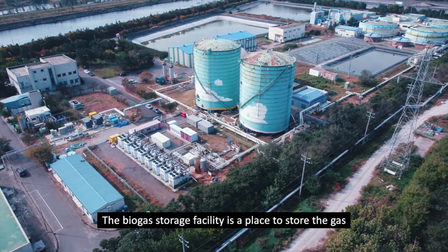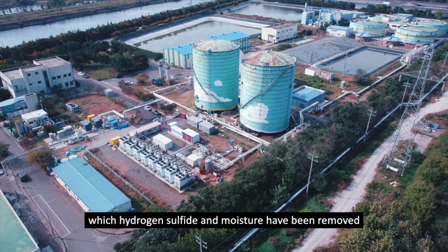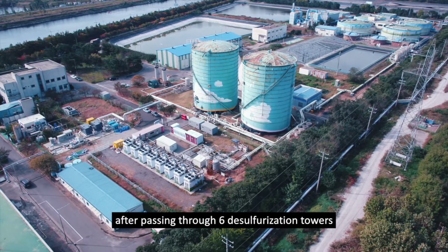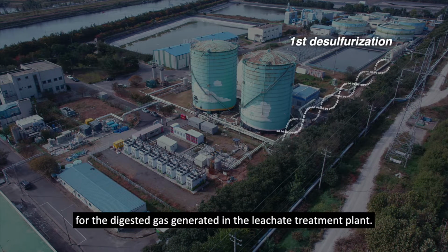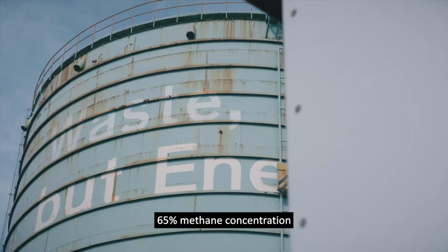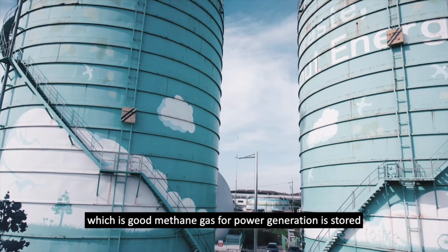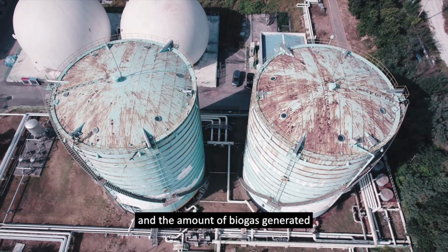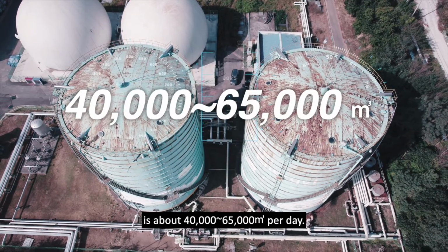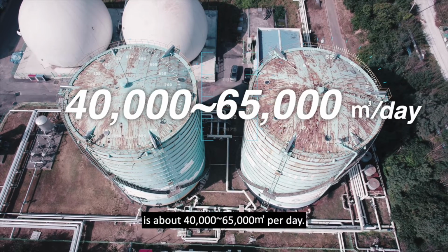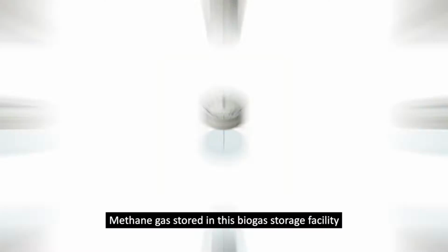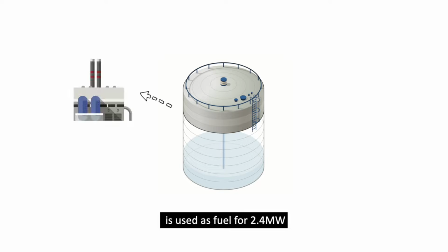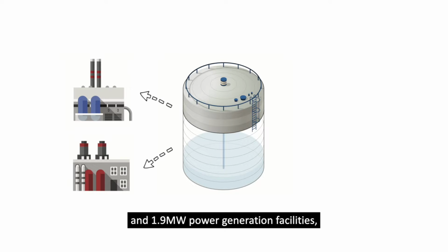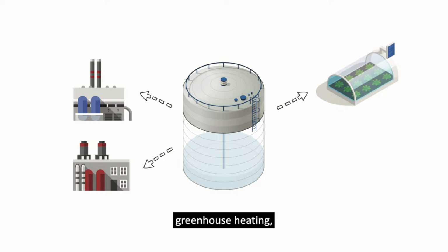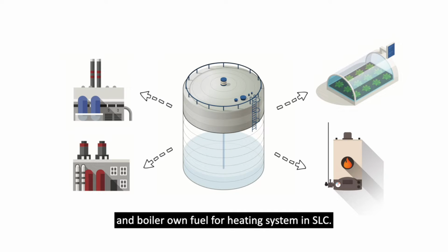The biogas storage facility is a place to store the gas from which hydrogen sulfide and moisture have been removed after passing through 6 desulfurization towers for the digested gas generated in the leachate treatment plant. A 65% methane concentration, which is good methane gas for power generation, is stored, and the amount of biogas generated is about 40,000 to 65,000 cubic meters per day. Methane gas stored in this biogas storage facility is used for fuel for 2.4 megawatt and 1.9 megawatt power generation facilities, greenhouse heating, and boiler fuel for the heating system in SLC.